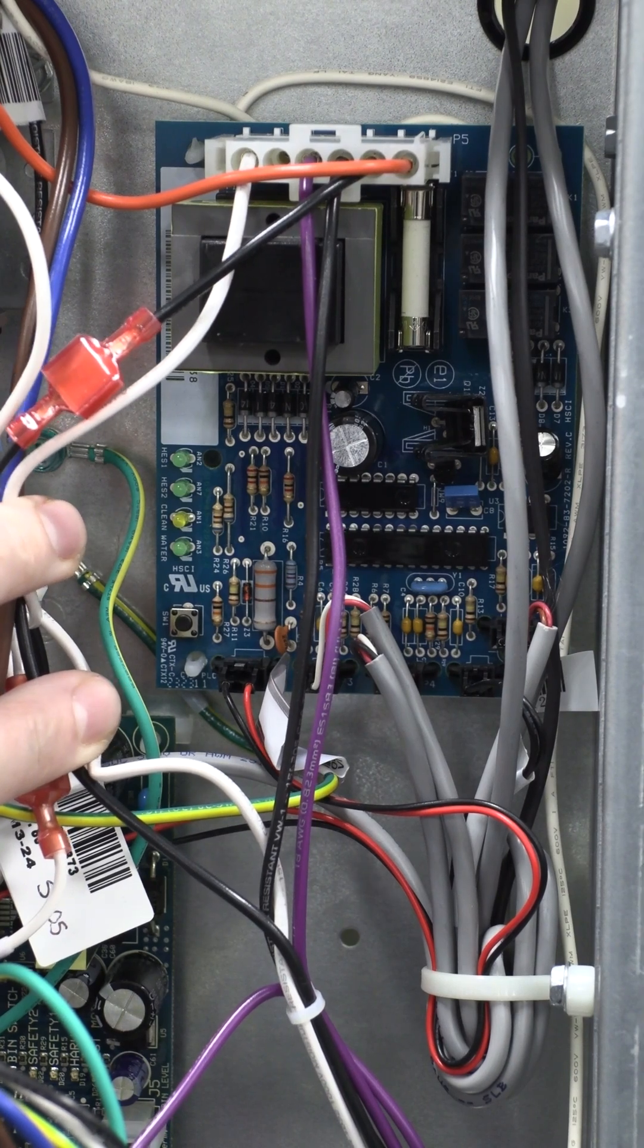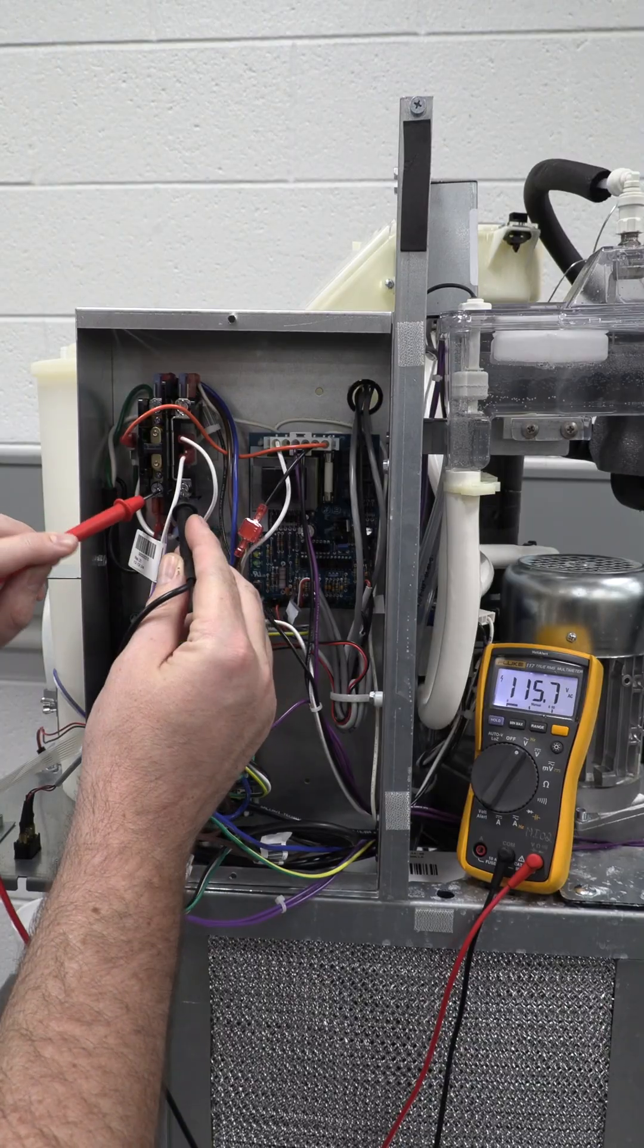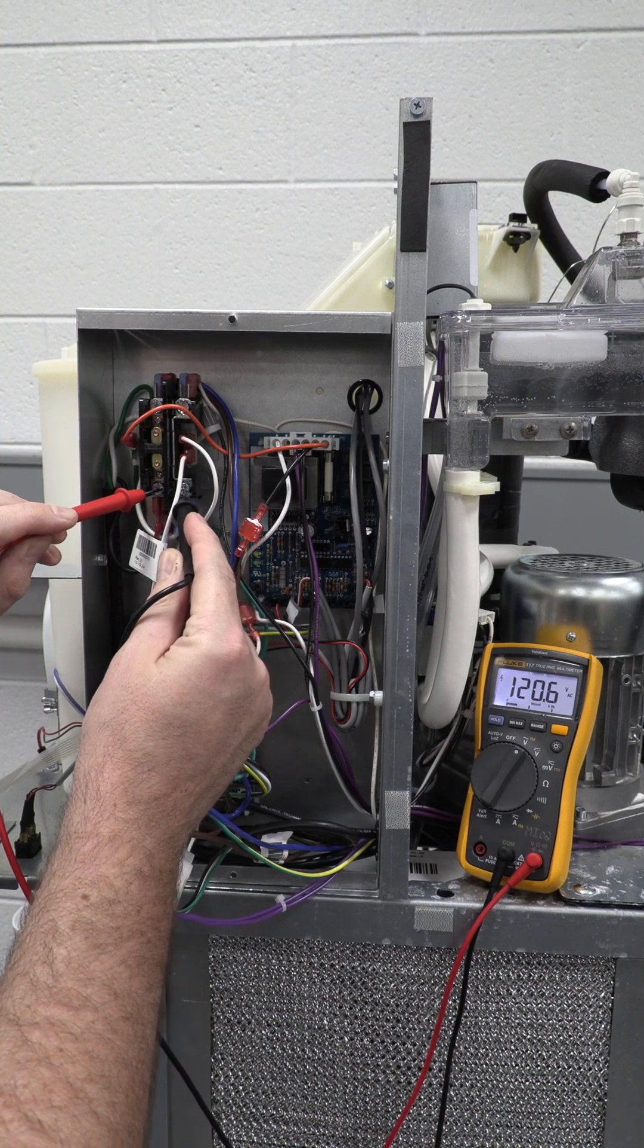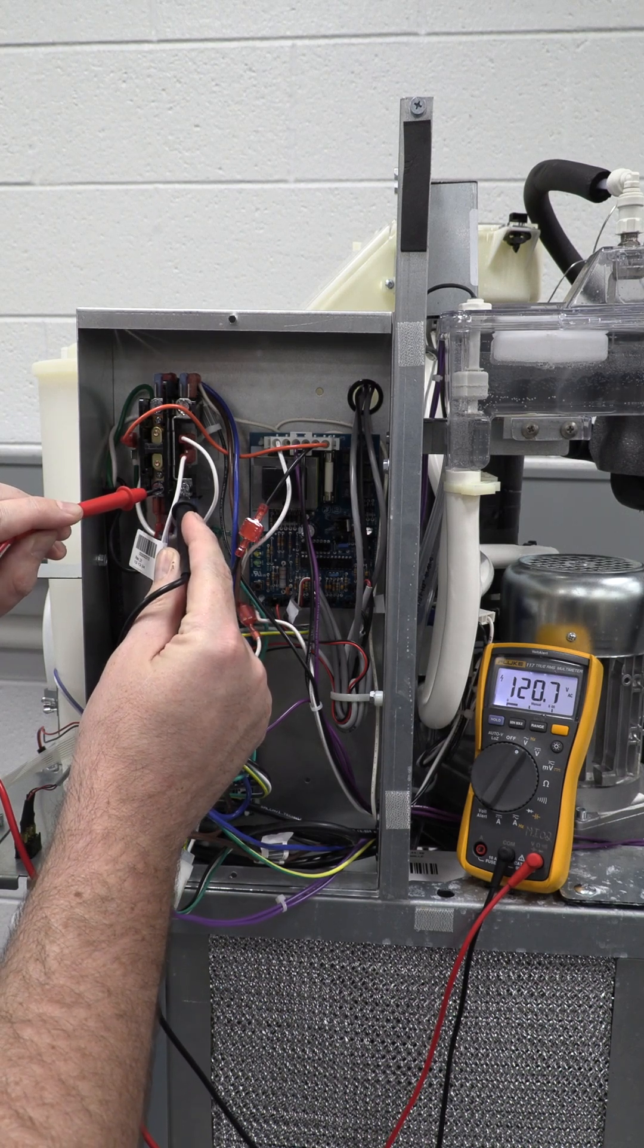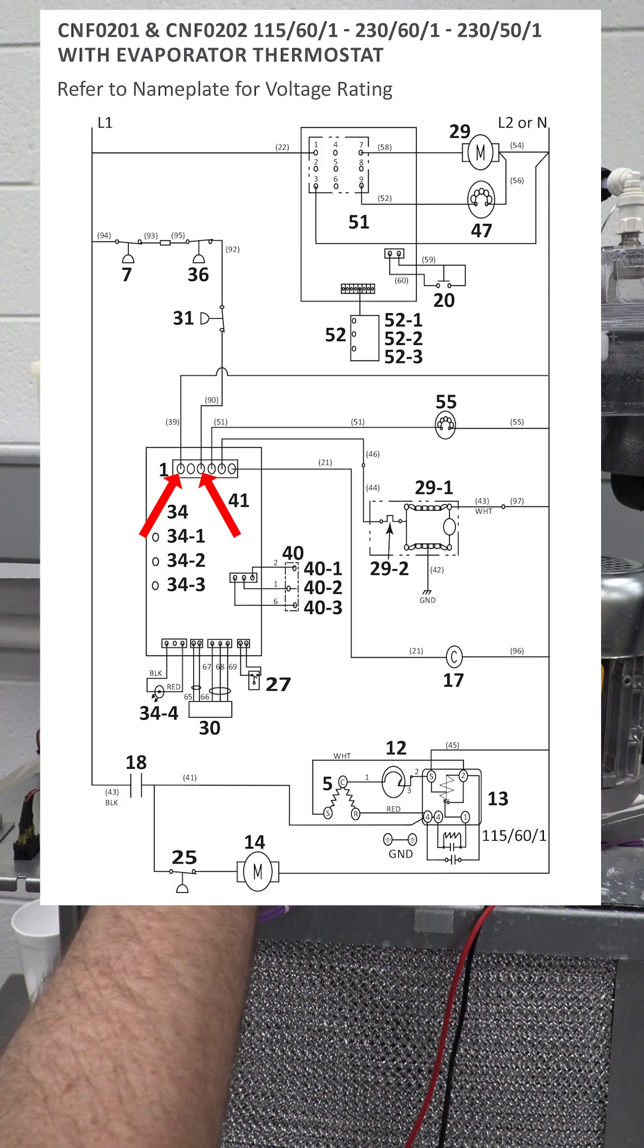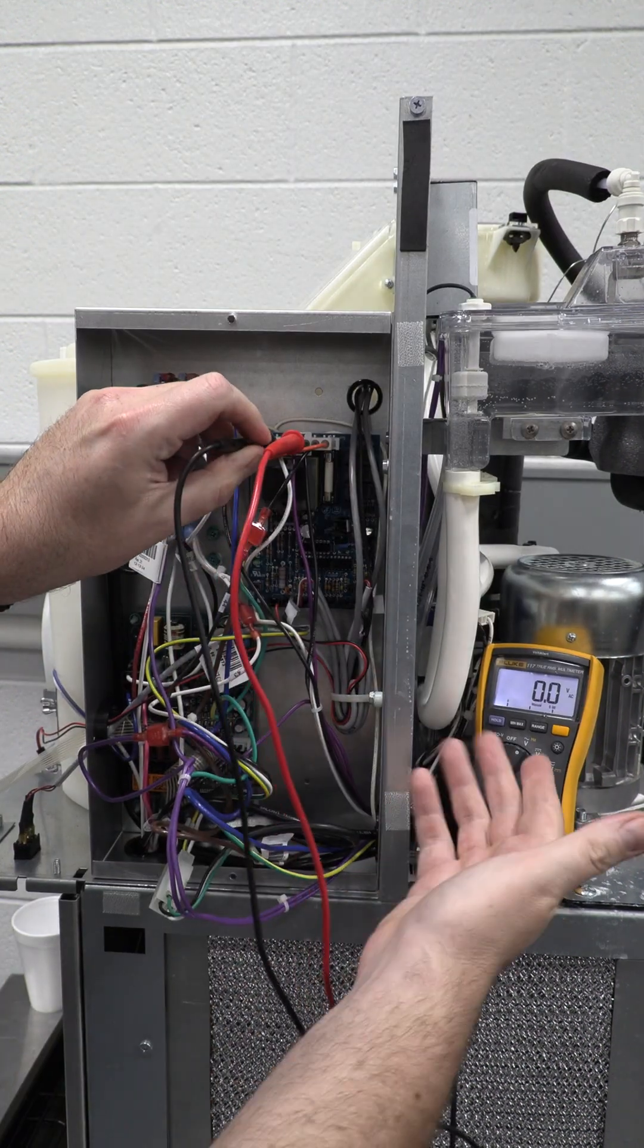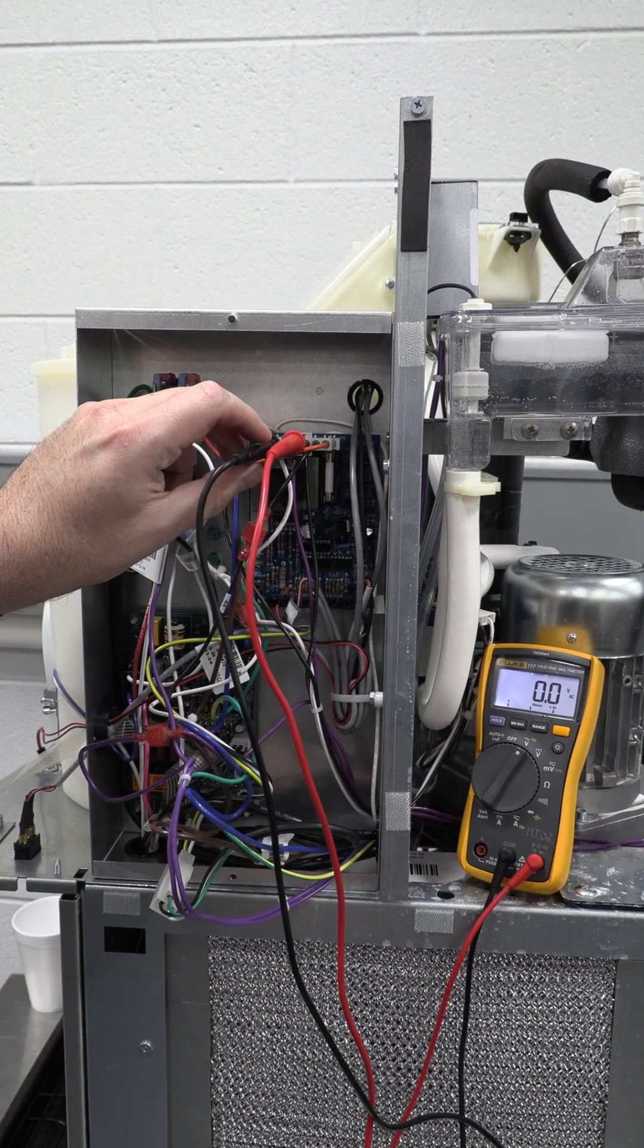If we take a look at our top board, which is our ice making board, you see that none of the lights are lit on this particular machine. We bring our line voltage in on the bottom, so you can see I have good line voltage coming into the machine. Next thing we're going to do is check for power between the purple wire and the white wire on the six pin connector, and as you can see I do not have voltage coming into this board.